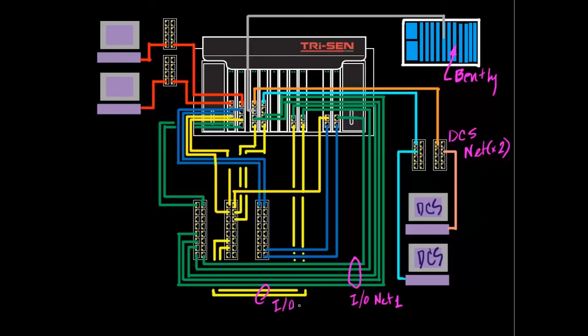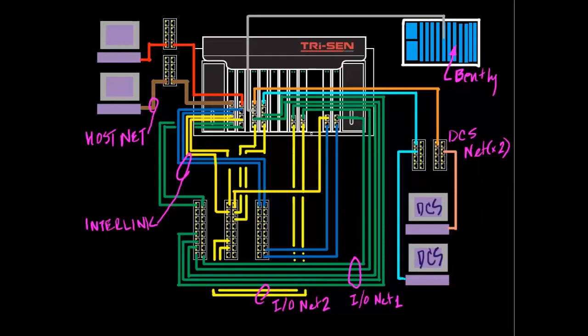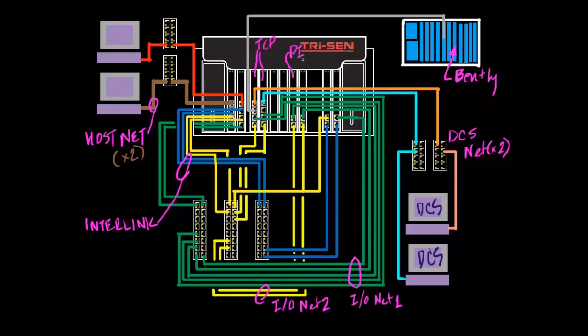And if we had redundant Bently communication we could use that second master port. So we have the Bently chassis, dual DCS networks, three I.O. networks. We call those I.O. net one and two. And then the blue network is what we call the interlink. It's used also by the node processors for communication between the two processors if that link is available. We have a host network. I've changed the color of one of those to brown so that those could be differentiated as well. And then we'll just identify the two extra boards that we put in the system.